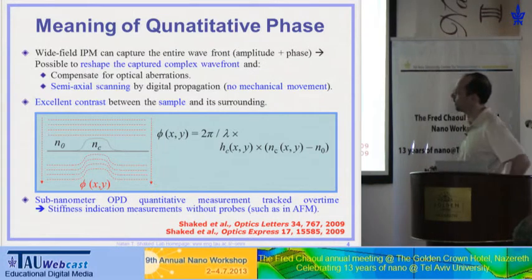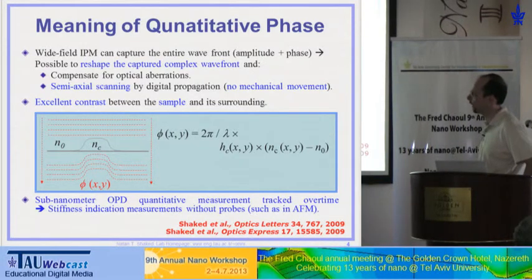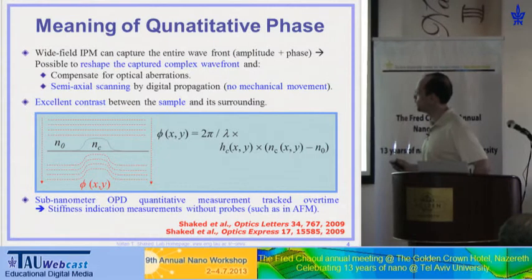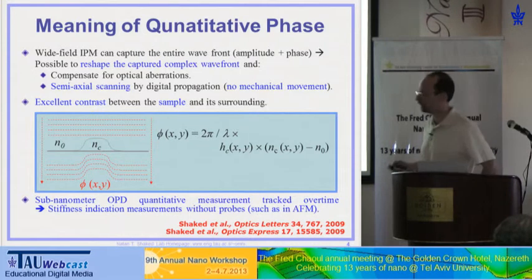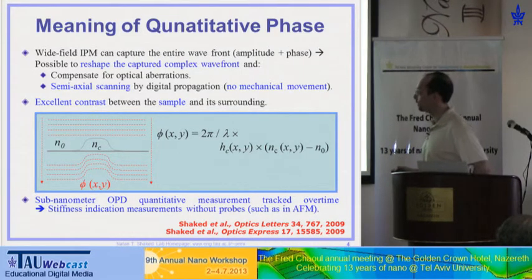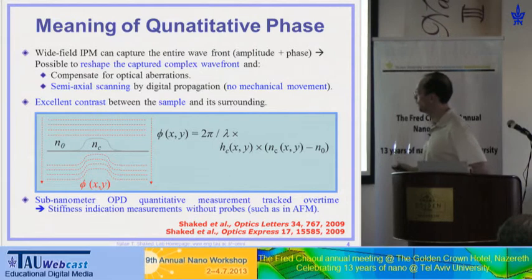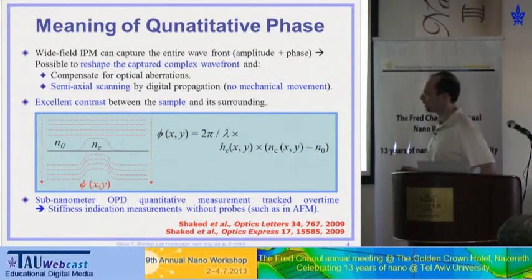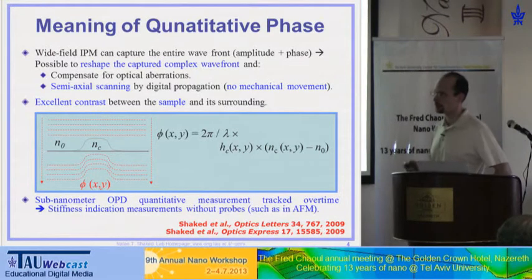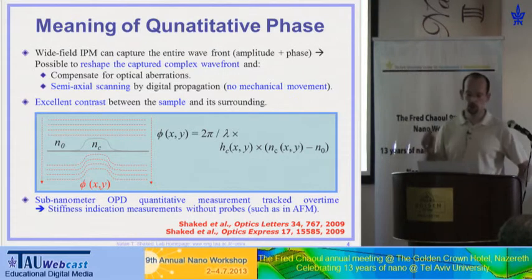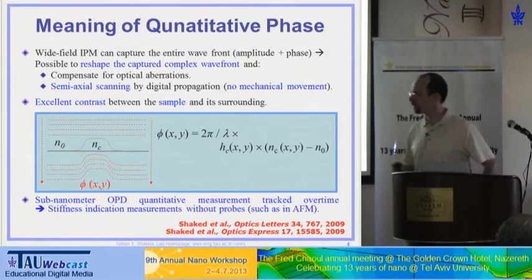I immerse the sample in a medium or have air, so I know the refractive index of the medium. I am actually measuring the difference between the refractive index of the sample — which might be a cell or an optical element — and the refractive index of the medium, which might be water or air. This difference is multiplied per each spatial point by the physical thickness of the sample. If the refractive index of the sample is known, I am able to get a physical thickness map — a two-dimensional map giving the physical thickness at each point.